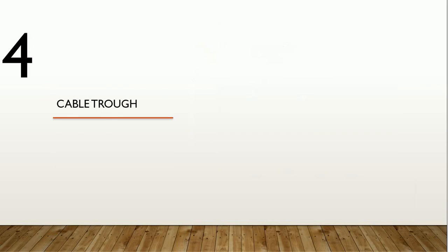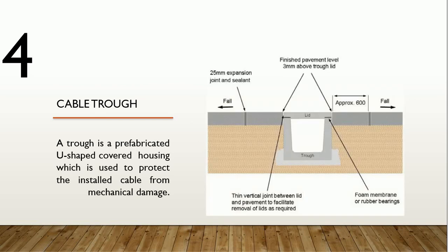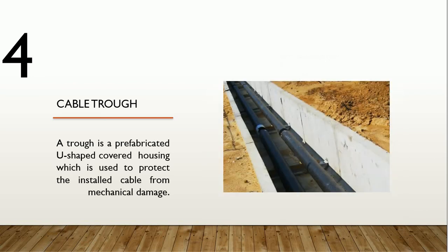The fourth type is cable trough, where a trough is a pre-fabricated U-shaped cover housing used to protect the installed cable from mechanical damage. As you see, the cable will be installed inside a U-shaped trough made of concrete and then covered with a cover that is also made of concrete.